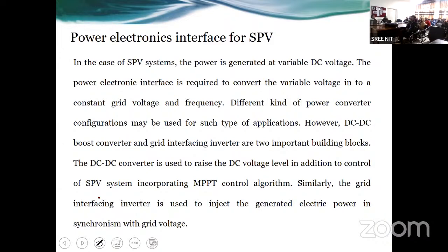because the grid is a big ocean. You cannot change its voltage and frequency. You can only inject into it. It is just like an infinite bus bar system. If you are from an electrical background, you know what an infinite source is. Infinite source means whatever amount of energy or power you supply in or take out, there is no effect in terms of voltage and frequency. So the grid is an infinite bus. You cannot change its voltage or frequency. What you can do is only inject or evacuate.